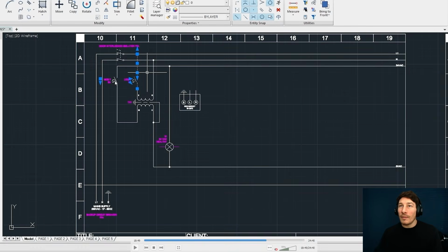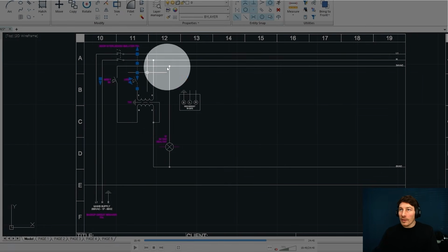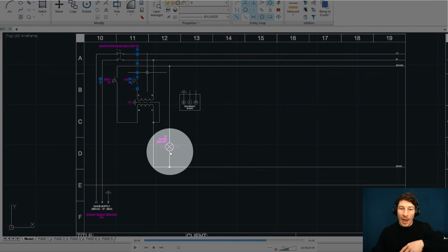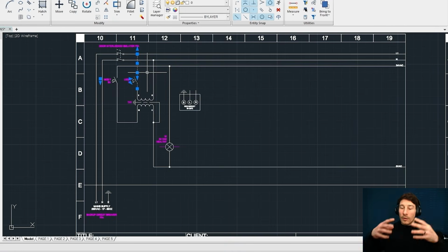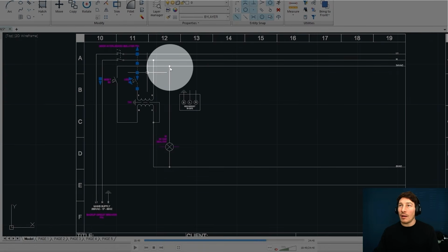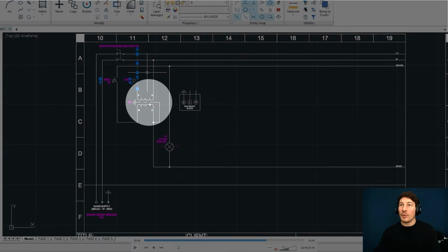And if this MCB on the secondary side for the 24 volt AC is okay, then we should have power here. So if we don't have power here, then it's like, right, how do we fault find this? And this is where you can think so much more logically when you understand the design process. So, first thing is, let's go upstream of that. This MCB, has this MCB tripped? No. Okay. Is this transformer working?